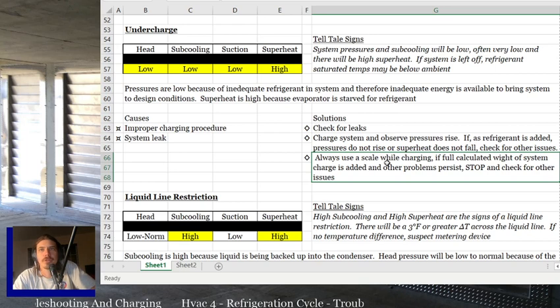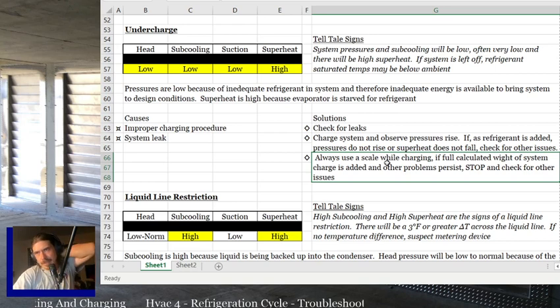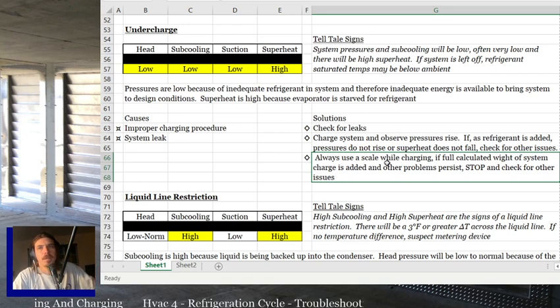So causes for undercharge are pretty easy, right? It's either improper charge or there's a system leak. It's got to be one of the two, pretty much. There's not many other things that are going to lead you to an undercharge. Either they didn't charge it right in the first place, or it's leaking out. So the solution is look for signs of leaks, look for oil, look for things that are leaking. If you don't see signs of oil or anything like that, then suspect maybe they just didn't charge it right in the beginning, or someone could have stolen some refrigerant out of it. I've never actually seen it happen, but they say it happens. So those are the issues you're looking for.